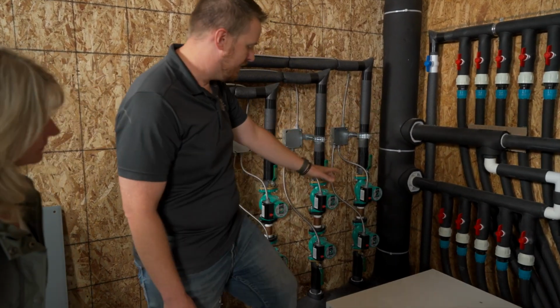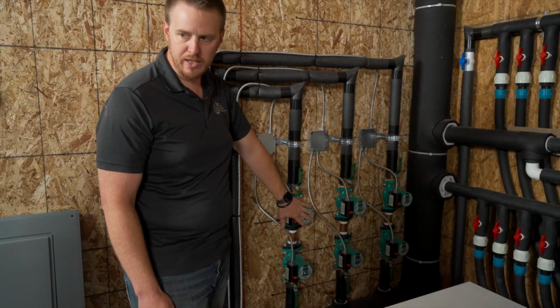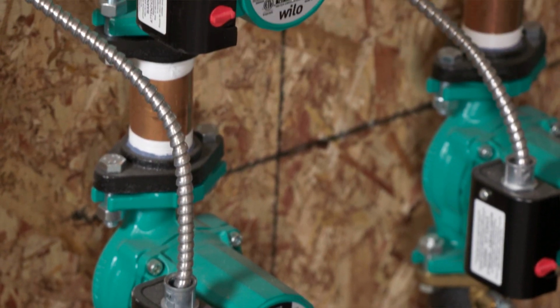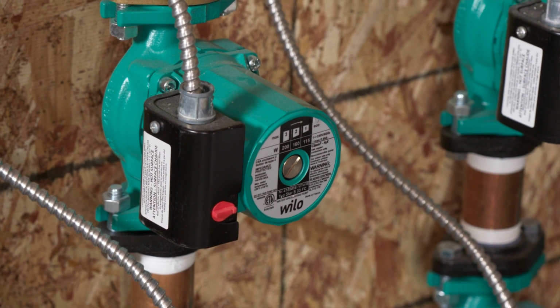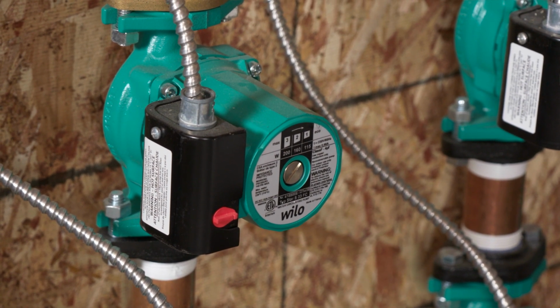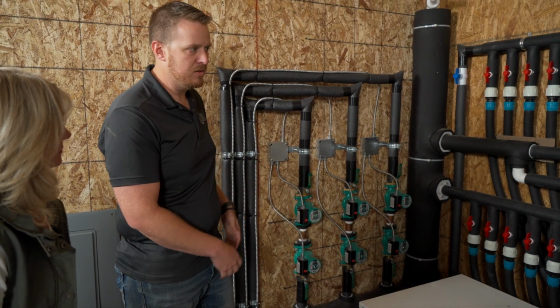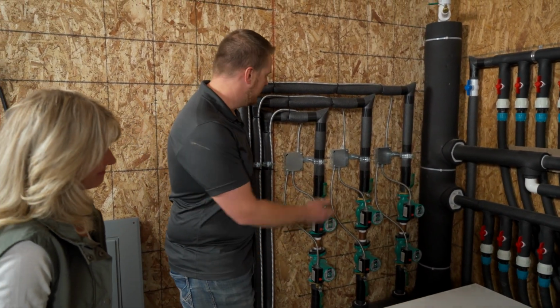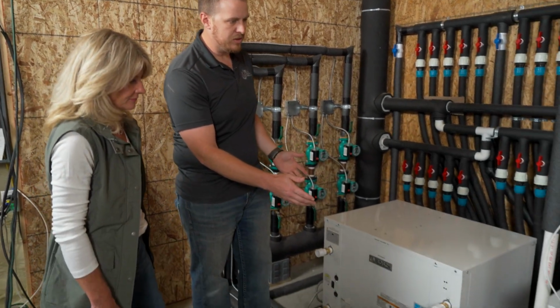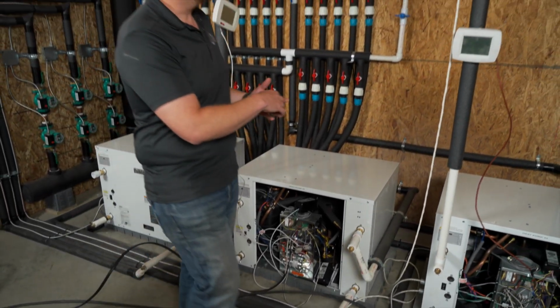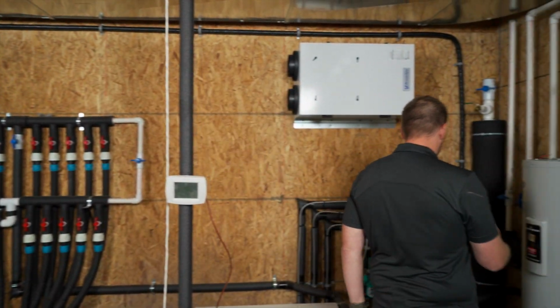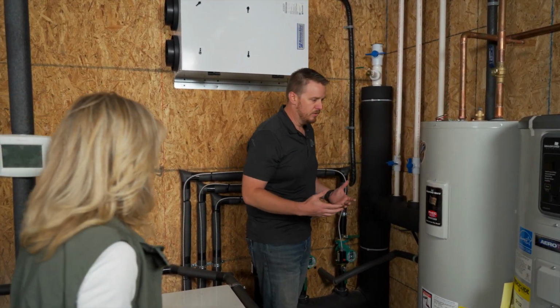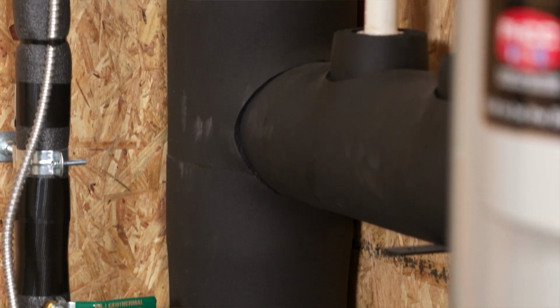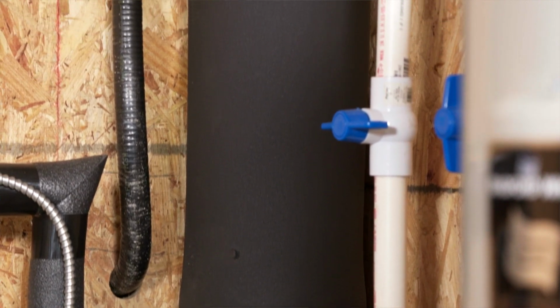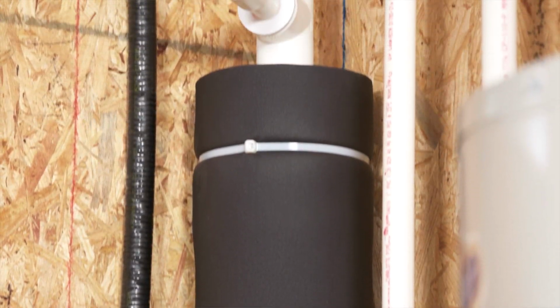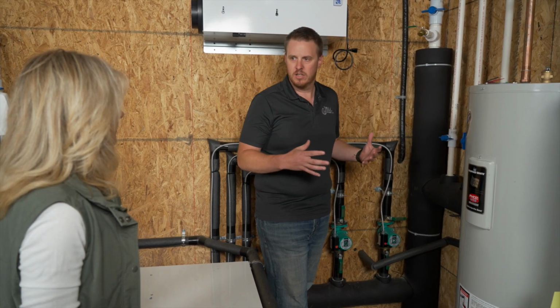From the standpipe, we come out to another manifold, and then we have our loop circulating pumps. These pumps are what are actually pushing the fluid through the ground and feeding the geothermal unit. We put isolation valves on the pumps. That way, if we ever have to change one out, it's very easy to do so and not have everything come out of the pipe. So the piping comes around, and then it hits our geothermal units. On this setup, we've got a few units. They all come over, and they start to feed into a buffer tank. Now, that buffer tank can vary depending on how much flow we need. On this particular project, we've got a lot of flow that can go out to air handlers, and we're not really needing as large of a buffer tank.